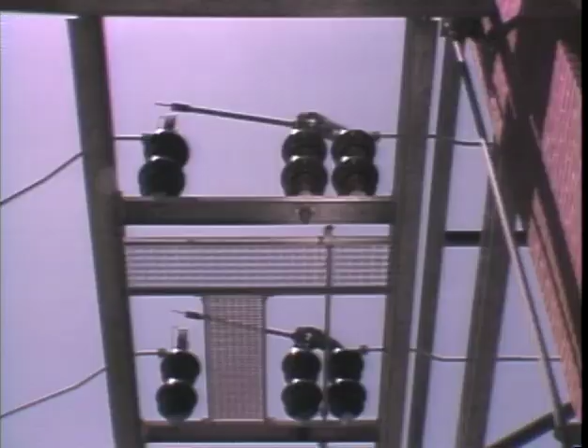Breaking a circuit under load can be dangerous, particularly if the circuit is carrying high voltage. That's because there's an increased chance of arcing when high voltage circuits are opened. Arcs can cause fires, injure personnel, and burn up equipment. And to keep you safe from the danger of arcs, circuit breakers are designed with special protective features. For example, arcs usually occur at the switch contacts where the circuit is broken. Now, that's why circuit breakers have contacts enclosed in a protective housing. This helps keep arcs contained and away from personnel and other equipment.